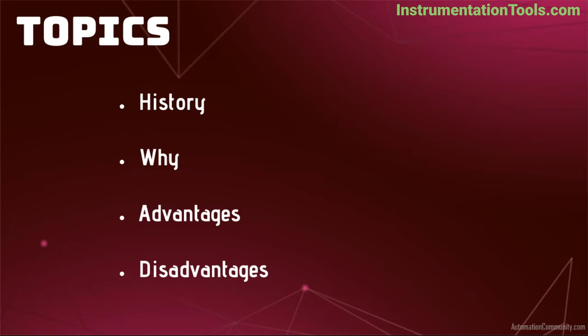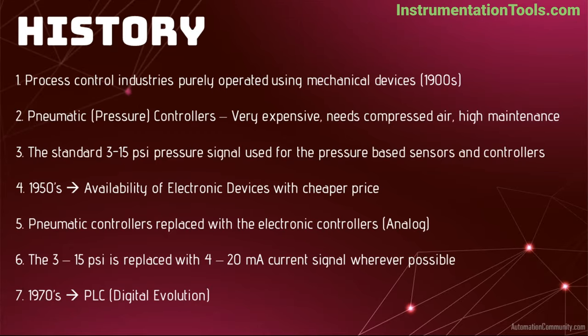Advantages and disadvantages. In the olden days, industries were equipped fully with mechanically operated devices like pneumatic sensors and controllers. Pneumatic means pressure. Pneumatic devices use pressure as a medium for the measurement and to control applications in the industries. Pneumatic devices generate an output signal in the range of 3 to 15 pounds per square inch. The 3 PSI represents 0% of the measured process variable, and the 15 PSI represents 100% of the measured process variable.